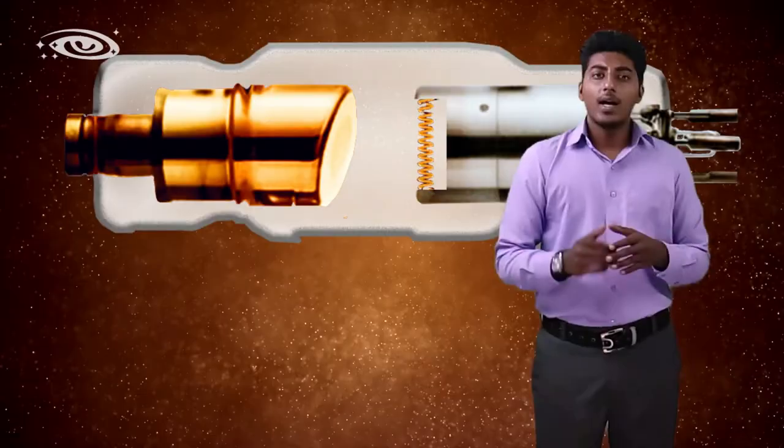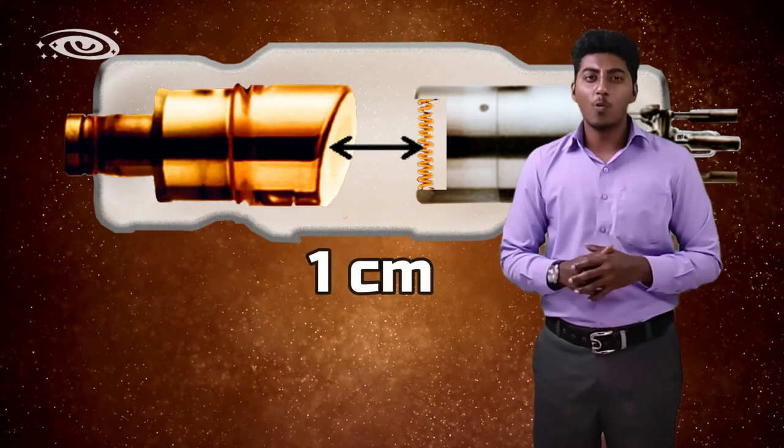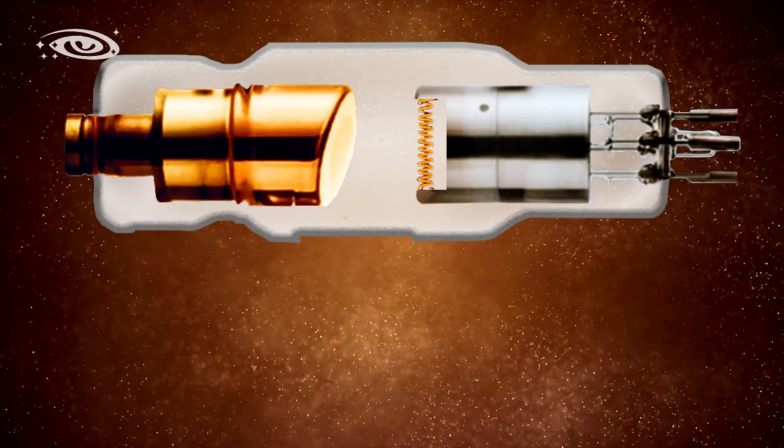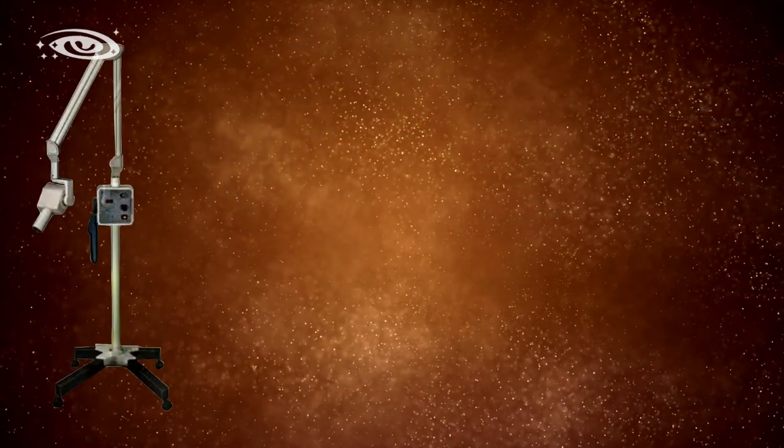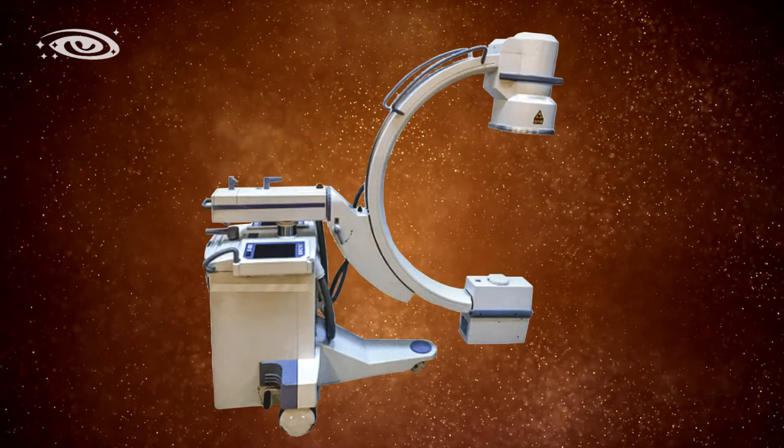The distance between the anode and cathode is maximum one centimeter. These stationary anode x-ray tubes are used in dental machines, portable and mobile machines, and C-arm machines.